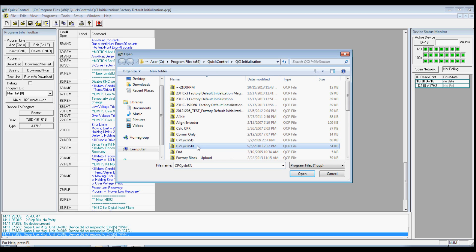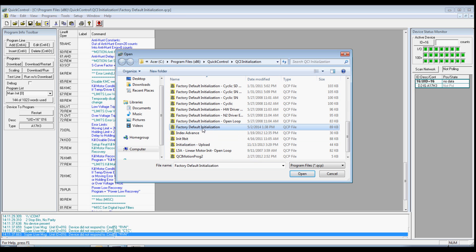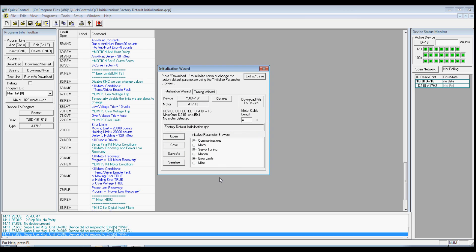For this tutorial, we will be using factory initialization. Select the file, click Open. Now enter the motor cable length in feet. This can be found on the last two digits of the cable part number. If your motor is directly connected to a controller, enter 1 for cable length. I am using a 4-foot cable so I will leave 4 as the cable length.